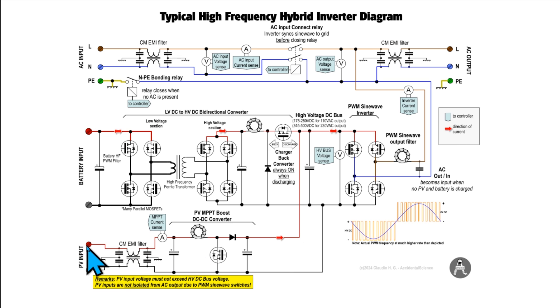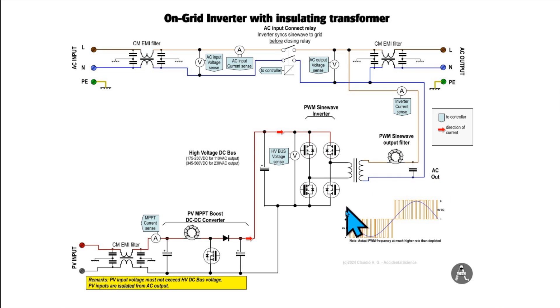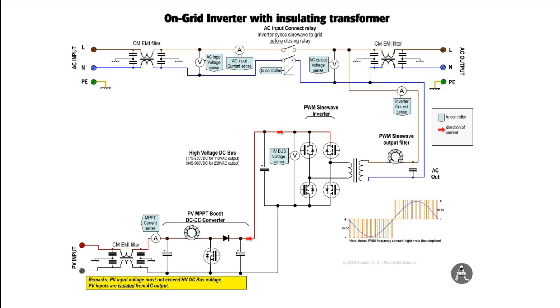The difference with the inverter that has the insulating transformer is here, is this that we have here an insulating transformer that insulates the high voltage DC bus in respect to the AC line. But this part is expensive and introduces some losses. And because inverters tend to have the best efficiency, let's say we have 95 percent, even few percent here have their weight. Basically in modern inverter this part is removed altogether and we have this configuration here.